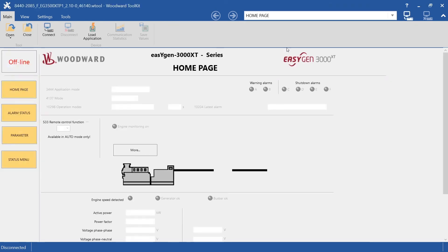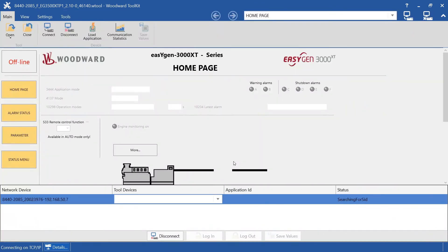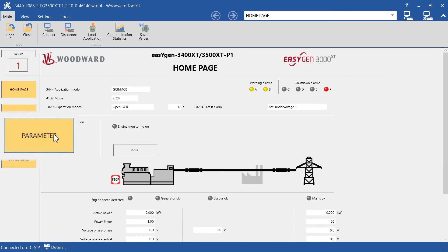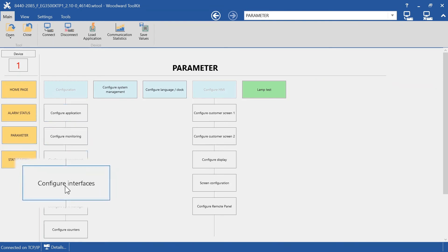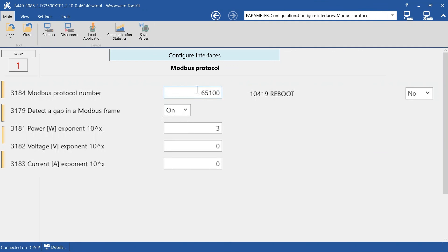Connect to your controller and enter the password. You can find more on the password system in the technical manual. Go to Parameters, then Configure Interfaces, then Modbus Protocol. Change the number of the protocol to correspond to your customized number. After changing the protocol number, remember to reboot the unit.